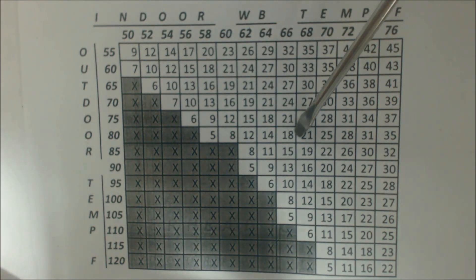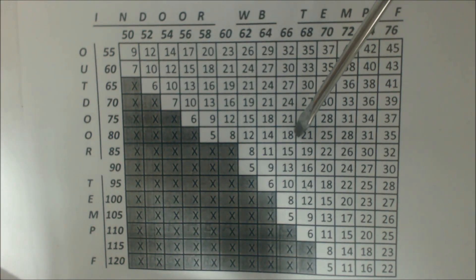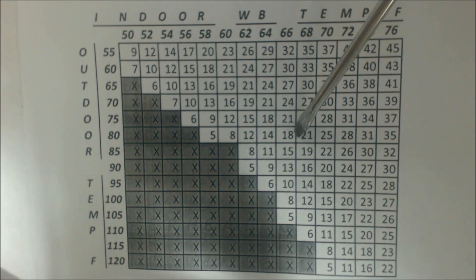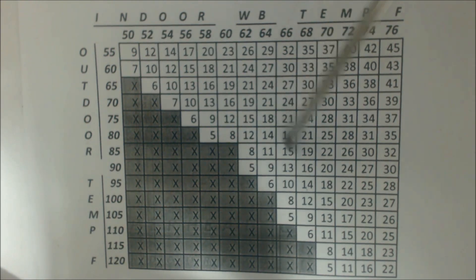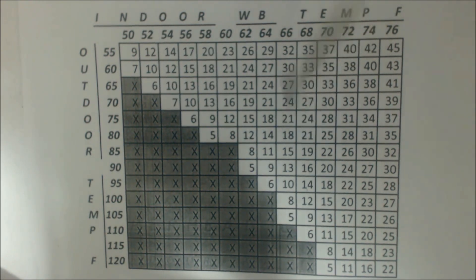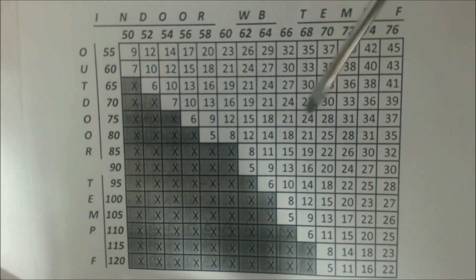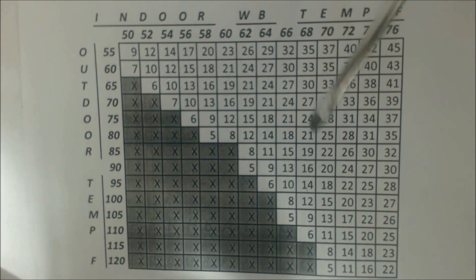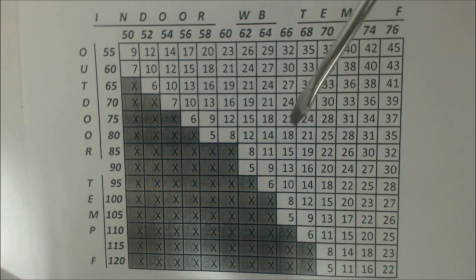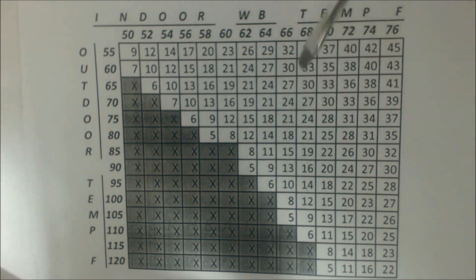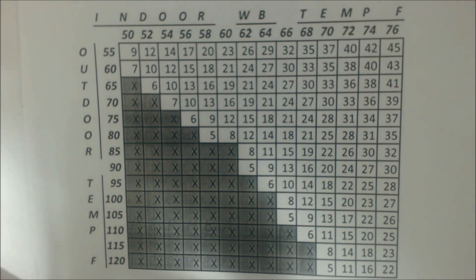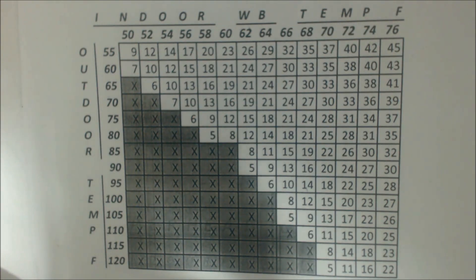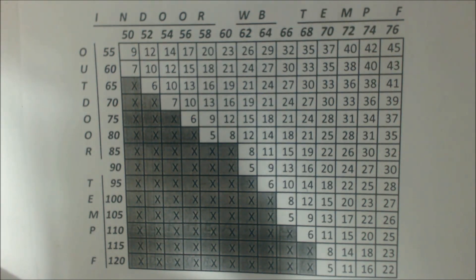If it's 18 degrees of superheat as the target, then you want to get to 18 degrees or maybe 17 degrees. You want to get real close to it. And then you can confirm your refrigerant charge with 18 to 21 degree temp difference between the return and supply, unless there's high humidity in the house, which you might have just a little lower than 18 to 21. But that's only if you have really high humidity in the house.